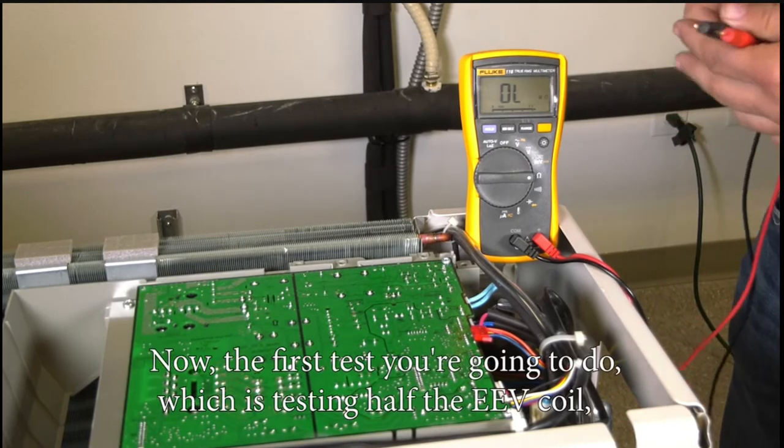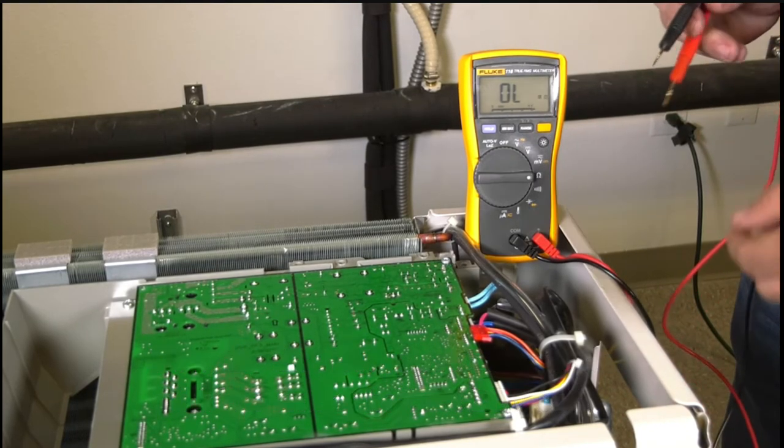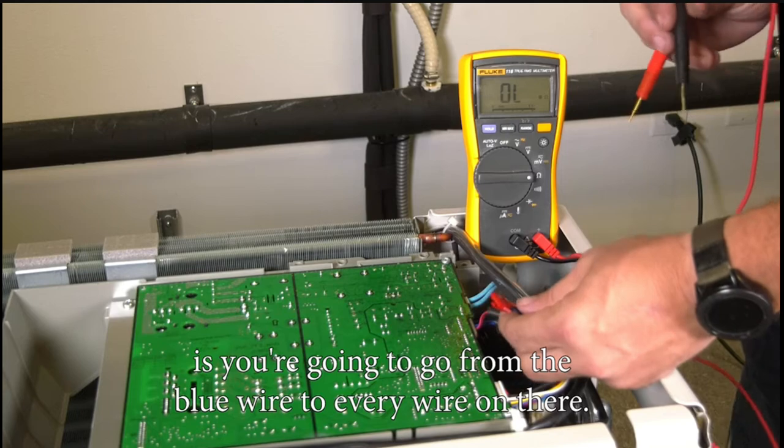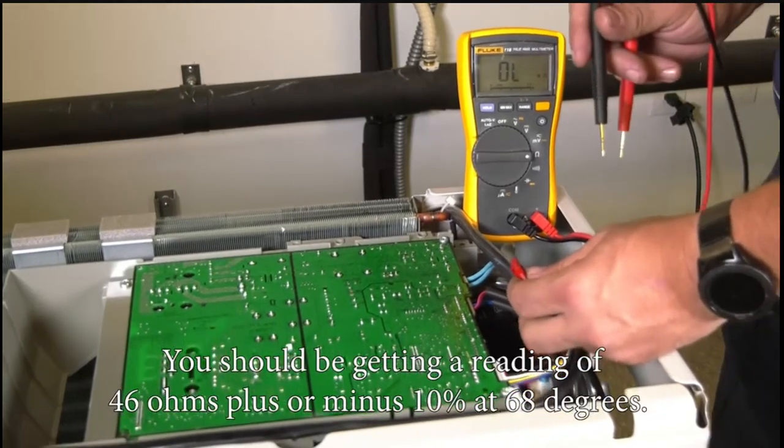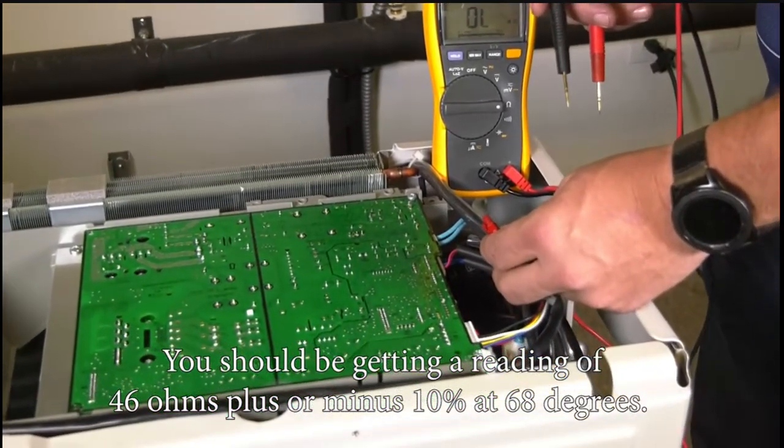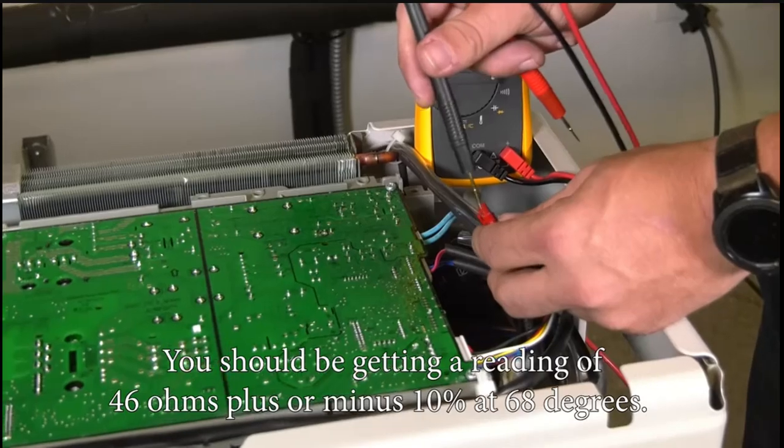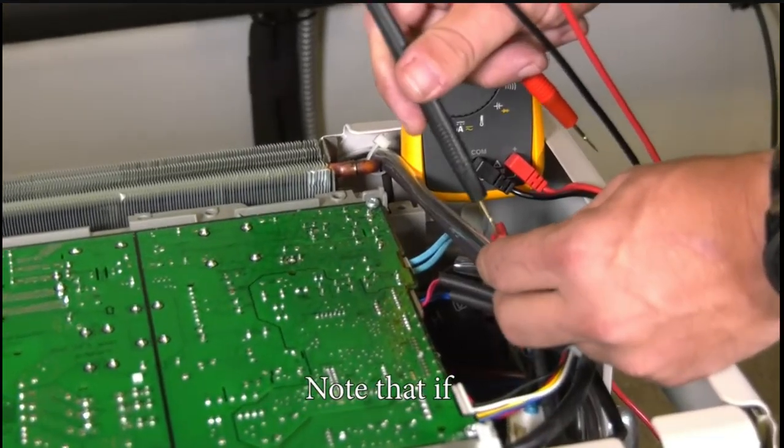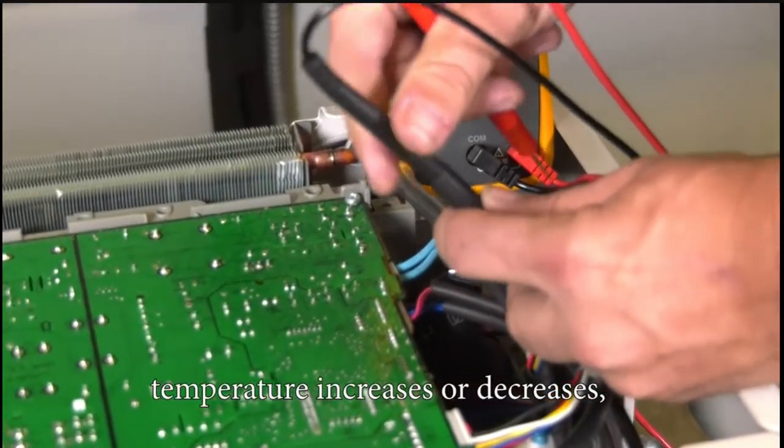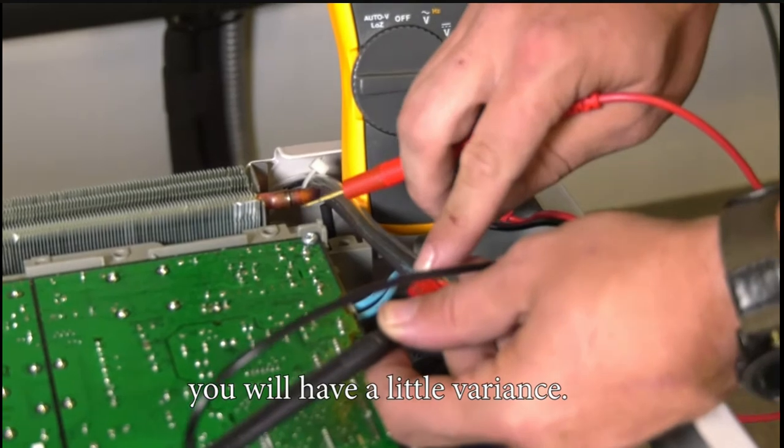Now the first test you're going to do, which is testing half the EEV coil, is going from the blue wire to every wire on there. You should be getting a reading of 46 ohms plus or minus 10 percent at 68 degrees. Note that if temperature increases or decreases, you will have a little variance.